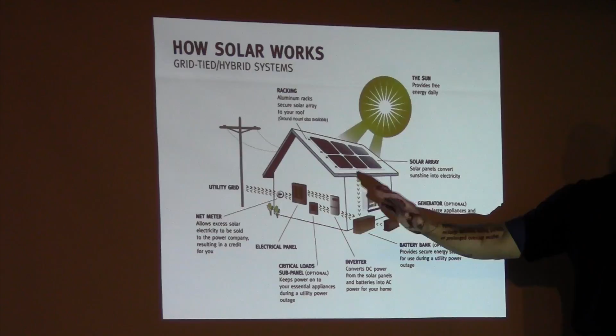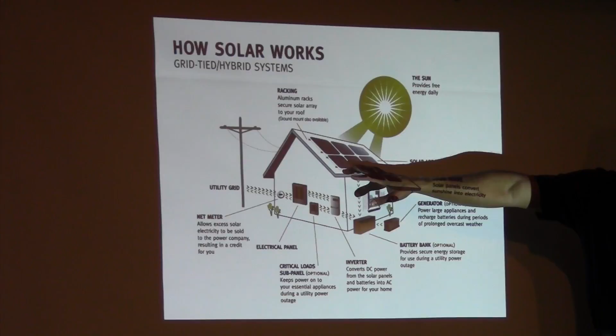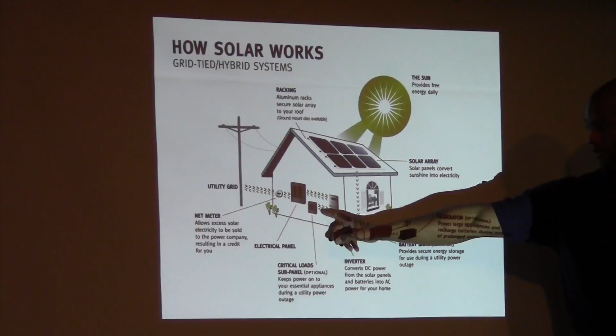Oh, so it doesn't do it automatically? No, a couple of things. The rapid shutdown requirement is automatic for grid-connected systems without a battery or generator. As soon as grid connection is lost, they've got to disconnect power all the way back up within 10 feet of the panels. Battery systems are different because they're designed as a backup power source, so even if utility drops out, your critical loads stay energized. But there are labeling requirements — you have to identify where all the power sources are and where the disconnecting means are, on a red and white placard.